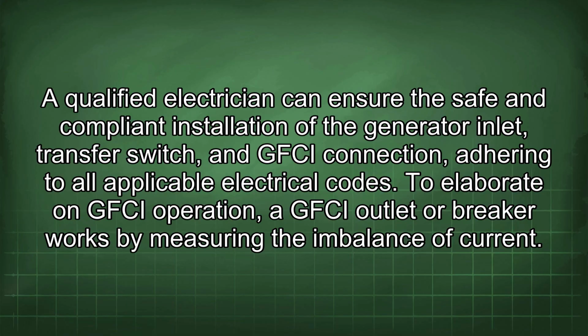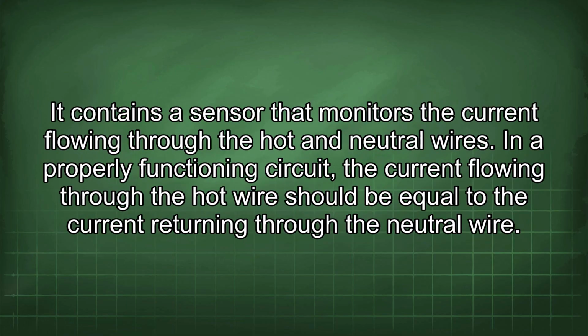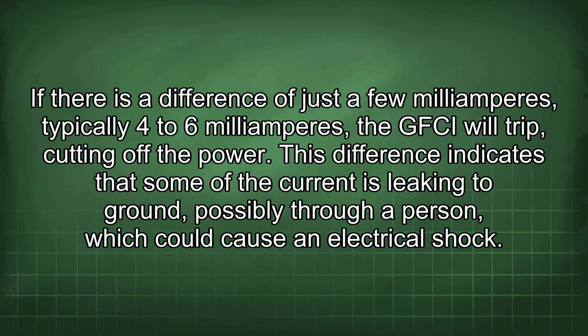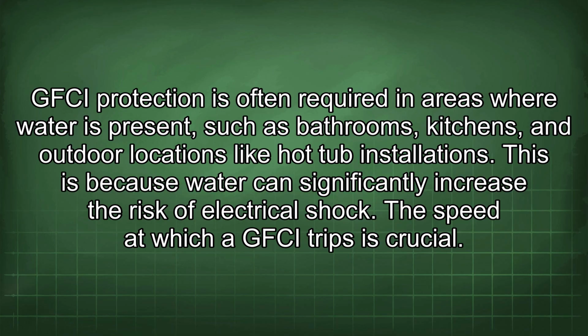To elaborate on GFCI operation, a GFCI outlet or breaker works by measuring the imbalance of current. It contains a sensor that monitors the current flowing through the hot and neutral wires. In a properly functioning circuit, the current flowing through the hot wire should be equal to the current returning through the neutral wire. If there is a difference of just a few milliamperes, typically 4 to 6 milliamperes, the GFCI will trip, cutting off the power. This difference indicates that some of the current is leaking to ground, possibly through a person, which could cause an electrical shock. GFCI protection is often required in areas where water is present, such as bathrooms, kitchens, and outdoor locations like hot tub installations. This is because water can significantly increase the risk of electrical shock.